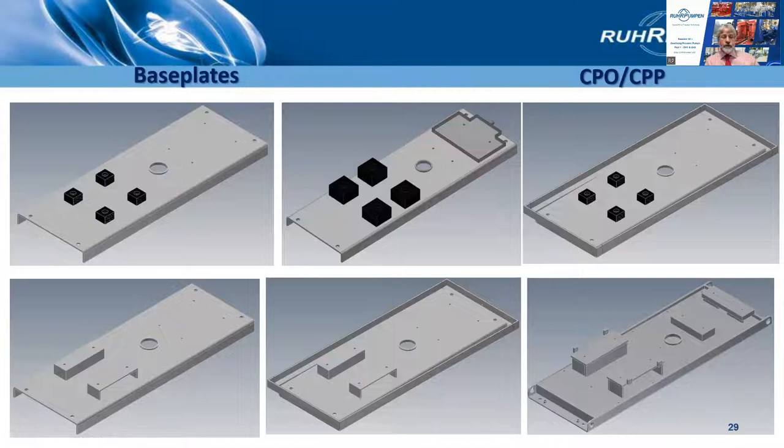And there are various different varieties of base plate which are specified in ANSI B73.1. Formed steel one with non-metallic motor support feet. Same again with a drain pan under the pump. A drain rim type. And the same again with metallic motor mounting feet. And in this case, with horizontal motor alignment jack screws.